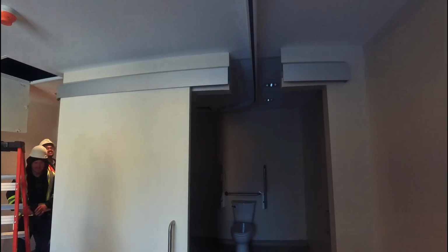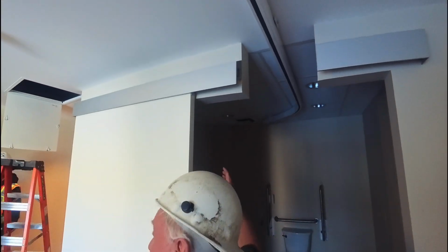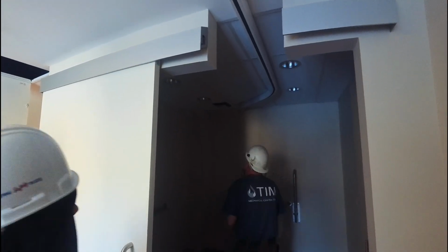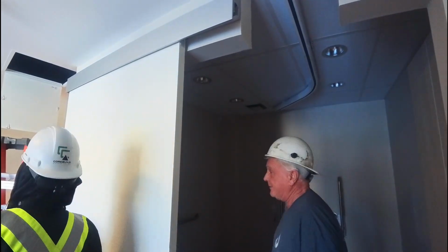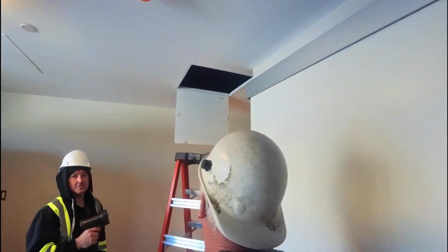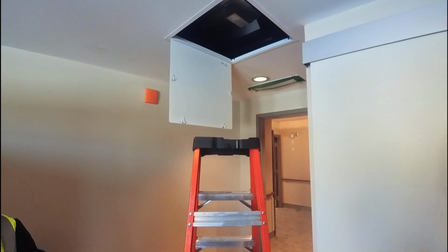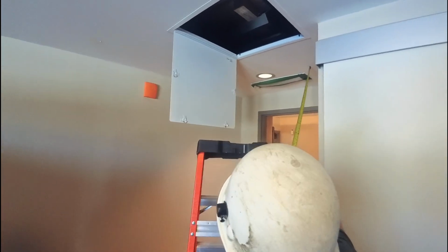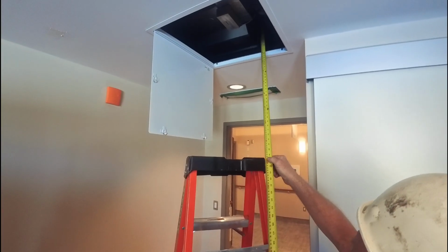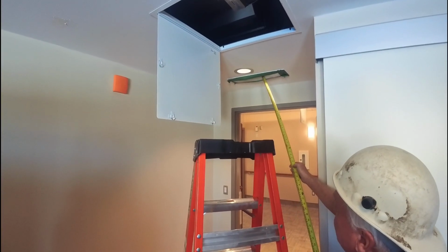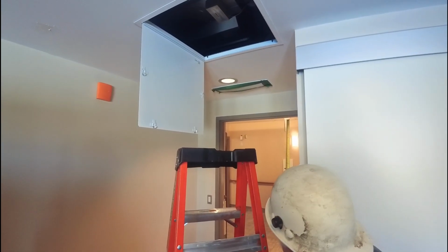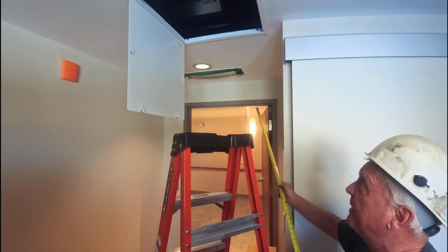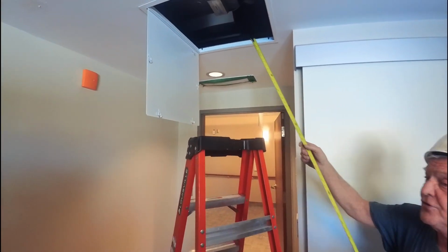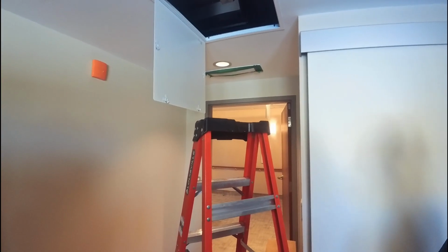And then on the exhaust side of each suite, coming from the makeup air in the hallway, each washroom has an exhaust grill, and they typically run at 50 to 70 CFM, just pulling out of the hallway. I think. Don't quote me on that. And the fresh air ties in. So yes, the fresh air ties into a plenum, which is at the back of the return end of the fan coil unit. That plenum is drawing air out of the suite as well through here, and it's also getting a feed of supply air out of the makeup air unit to assist in making sure we have enough return air in each individual suite.